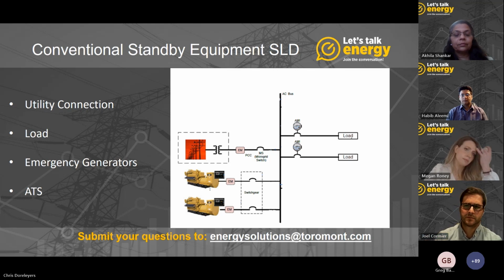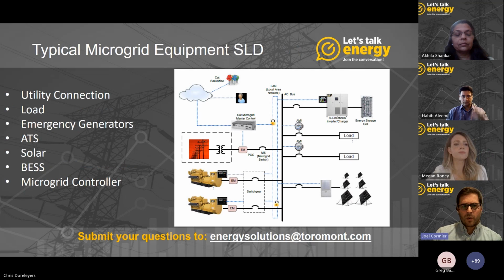Next slide, please. So on this slide, this image also reflects a typical single line diagram, but in this case, it not only includes the conventional sources that we just talked about, but it also includes renewable assets such as solar and the battery energy storage system, all managed by a microgrid controller. As you can see on the image, the batteries and the solar are now connected to that same common bus. And we can also see the little blue dotted line that connects the controls of all that equipment back to a microgrid controller. And that microgrid controller really acts as kind of the brains behind the operation.